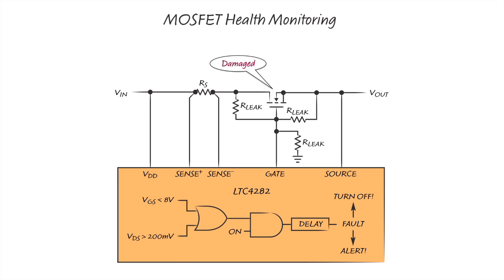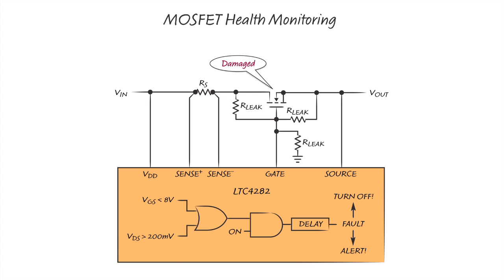To address this problem, the LTC4282 monitors the gate-to-source voltages of the MOSFETs as well as the voltage across the hot swap circuit to ensure that the MOSFETs aren't in a state where they are dissipating too much power. When these situations occur, the LTC4282 waits for a configurable time delay, then automatically turns off and generates alerts.